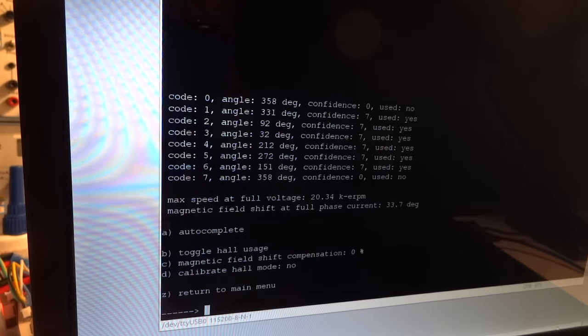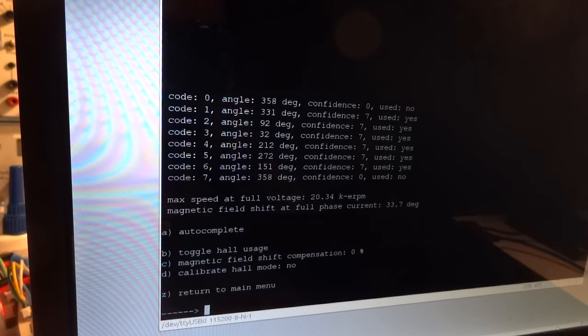If you use optical sensors, they also don't see the coil field, so you don't need compensation. Same for when you have an additional magnet on the end of your motor shaft and you're using some other type of encoder, then also you don't need to compensate. The only time you do need to compensate is when the Hall sensors are placed in slots in the teeth. Then this value needs to be set to 100%, but the default you get with autodetect is 0%, so no compensation.